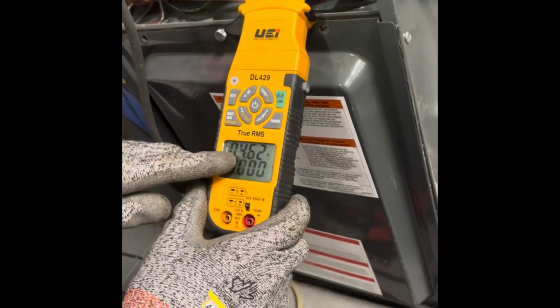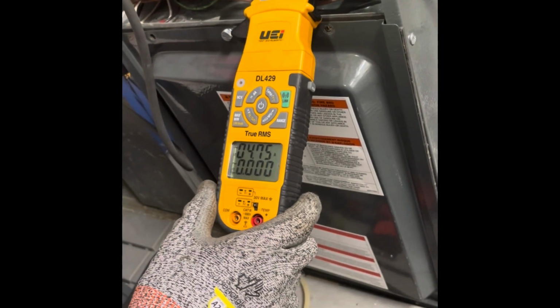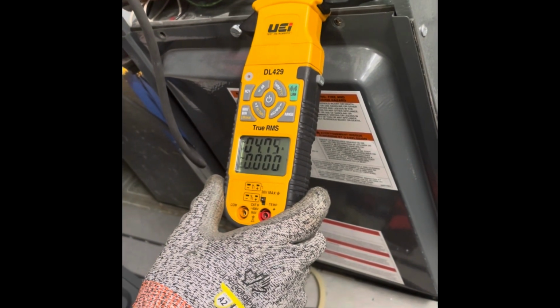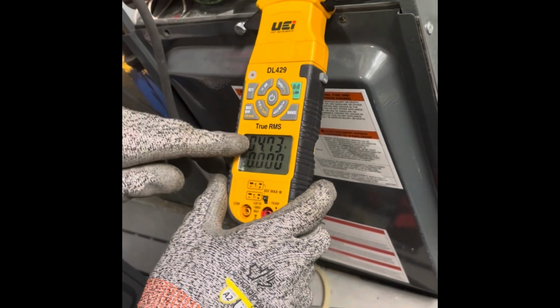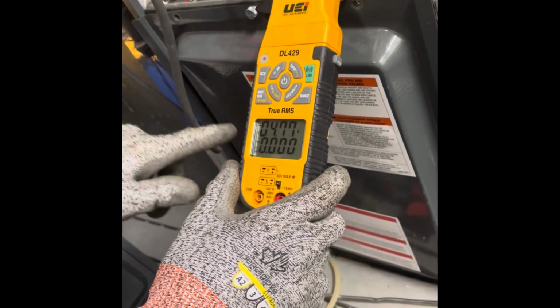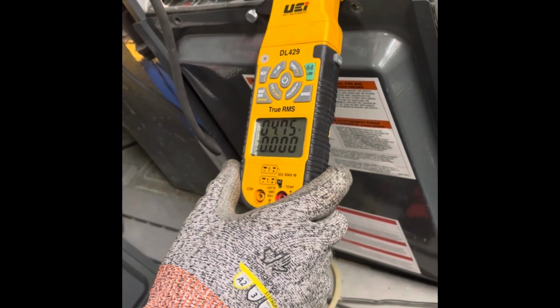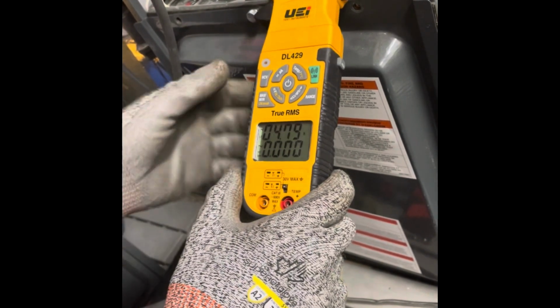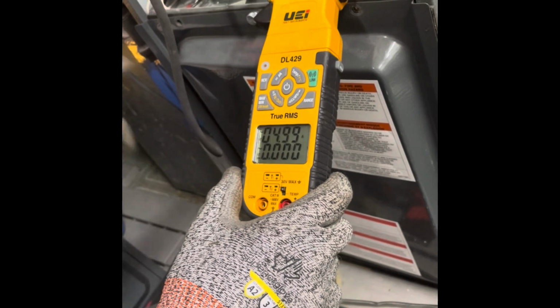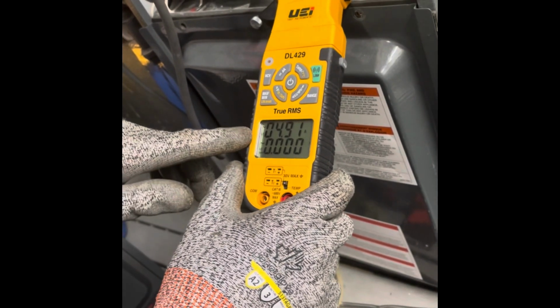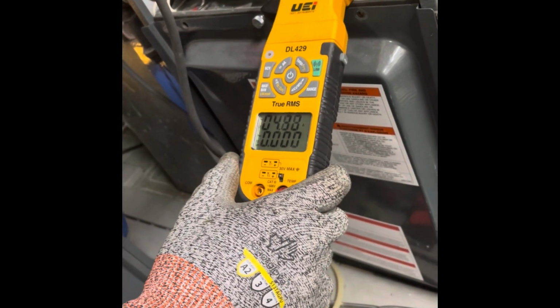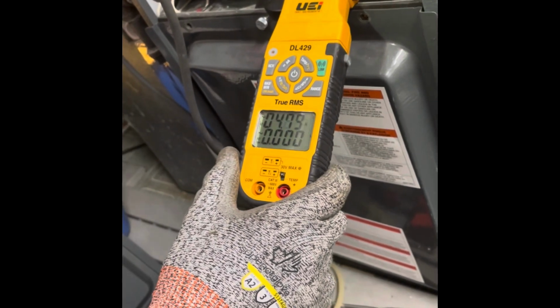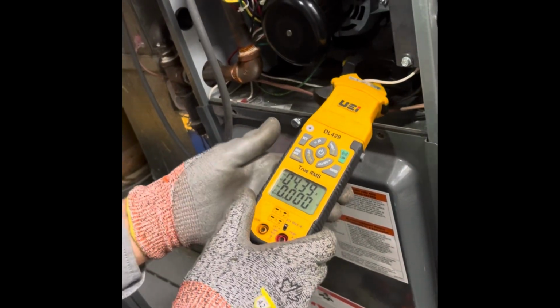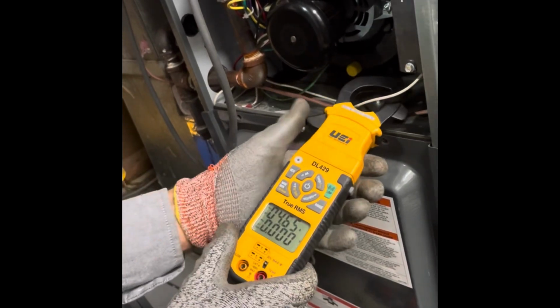Now, as for our electrical amp draw, if you look at our screen here, it was going 5.5, it's now 4.76. So this is the amp draw on our venter motor running, as well as our blower motor that moves the air through the house. If I had a reading over that sticker number, my eyebrows would be lifting up, because I predict that one of these motors is going to burn out soon. So I'm happy with the way the electrical test is here, as well as the operation of these motors.